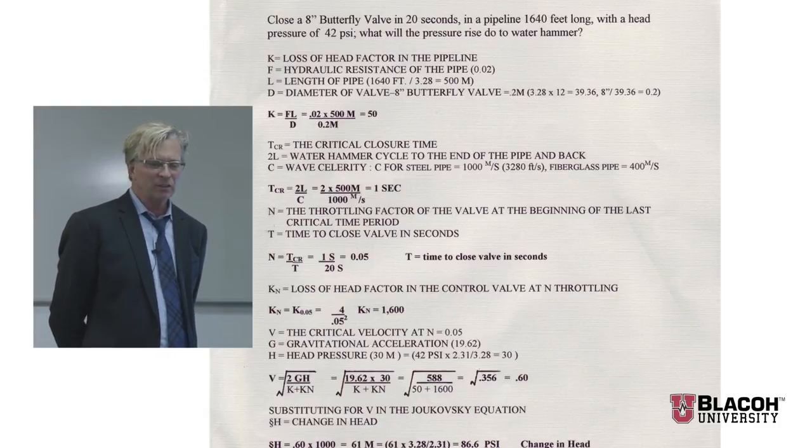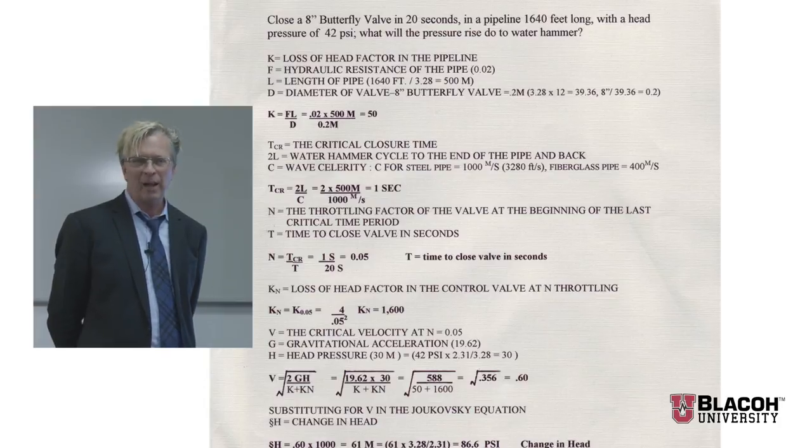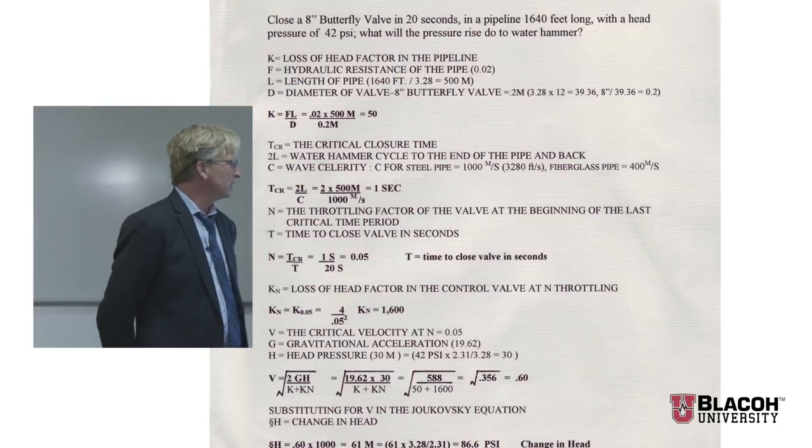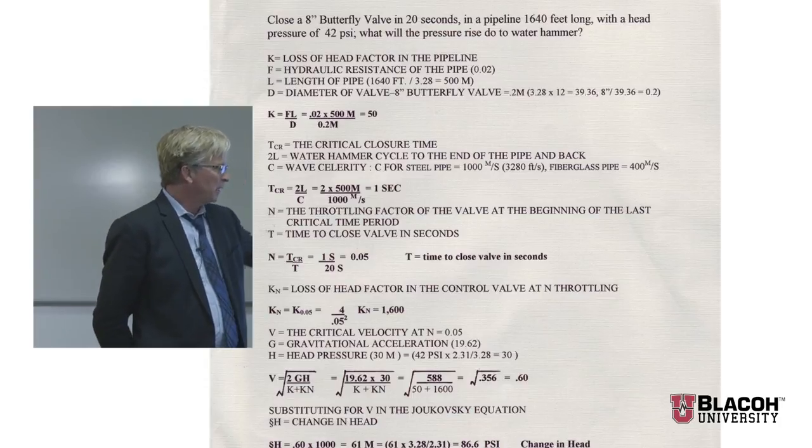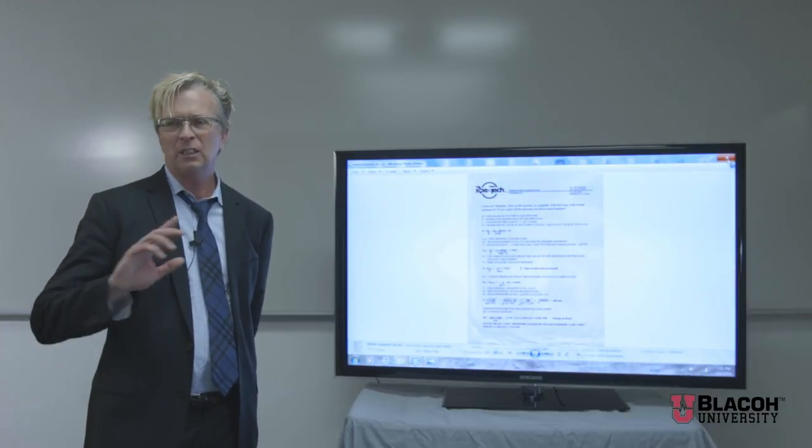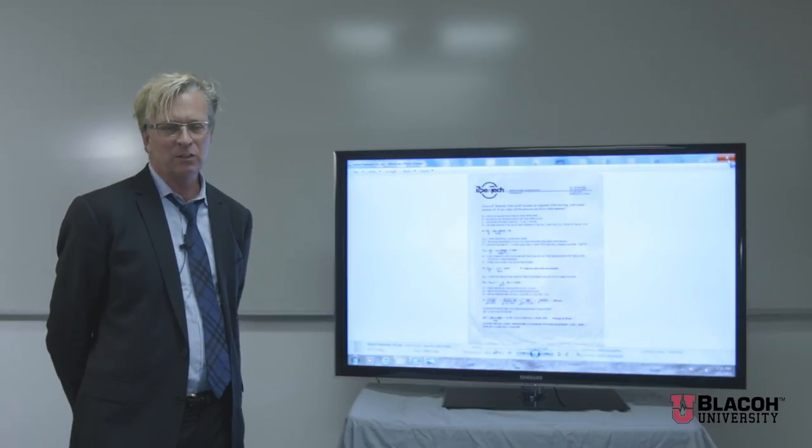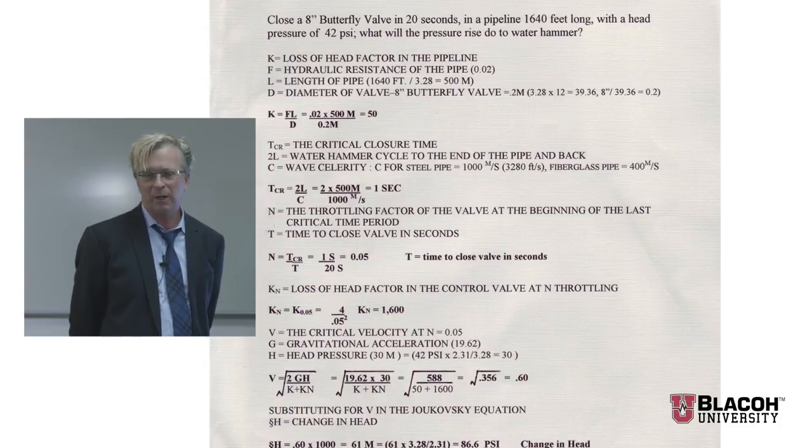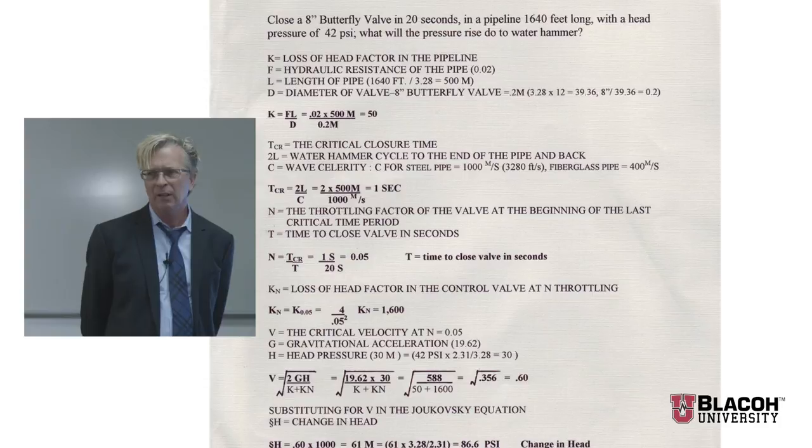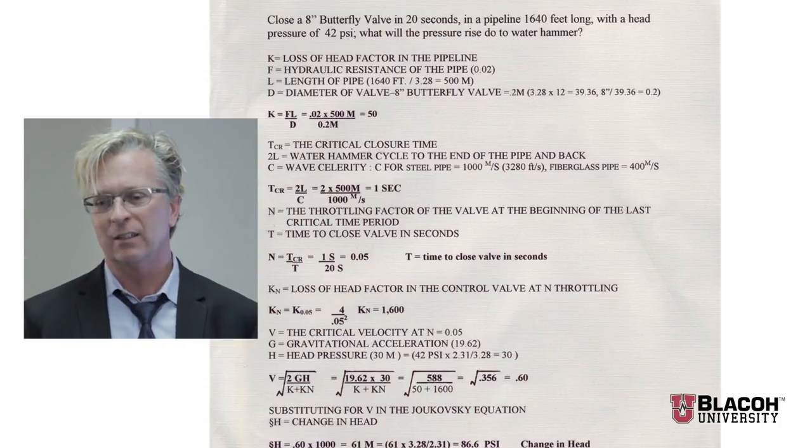To make it mathematically easy, we're dealing with a short run of pipe, 1640 feet long, 8-inch pipe. That wave oscillates out 1640 feet and back 1640 feet. We calculate the loss of head factor, hydraulic resistance, length of pipe, diameter to get our K factor. The critical closure time of the valve is that wave frequency traveling through the piping system, calculated as 2 times the length divided by the celerity of the wave. In this example we're using Schedule 40 pipe, 8-inch, with wave speed of 3280 feet per second.